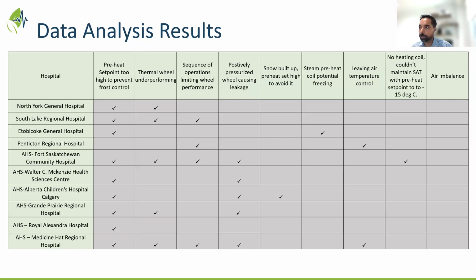There are more factors involved in different facilities, as you see. Some of them are unique to each facility, and some are common among different facilities. But preheat set point, thermal wheel underperforming, and sequence of operations are the key factors influencing the performance of the wheels. Then positive pressurization causing wheel leakage is more predominant in AHS sites, and I'll present a slide on that as well. And then there's snow buildup, which is unique to a couple of hospitals, or one hospital, where there's an issue limiting the factors as well. The steam preheat is also a limiting factor at one hospital. I'll touch on these in a second in the rest of the slides.